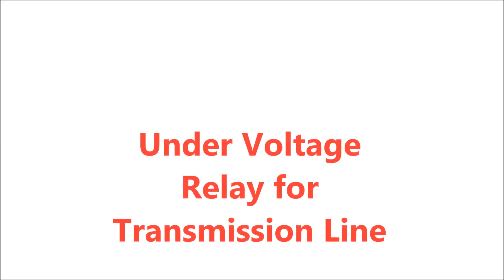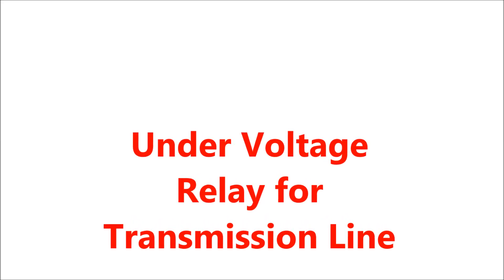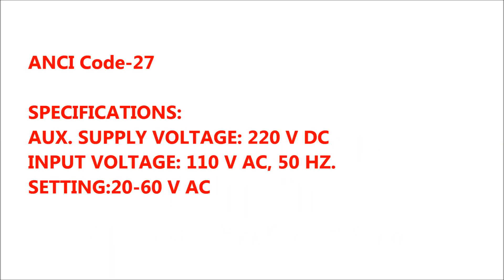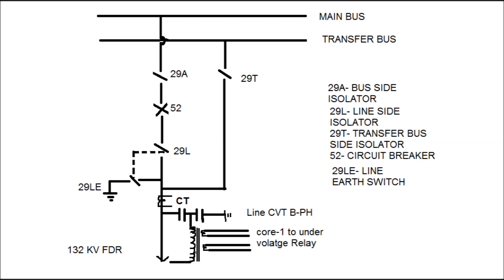The under voltage relay for a transmission line is represented as ANSI code 27. Generally, the auxiliary supply voltage is of the order of 220 volt DC, and the input voltage for the coil is 110 volt AC at 50 Hz frequency. The settings range is 20 to 60 volt AC.